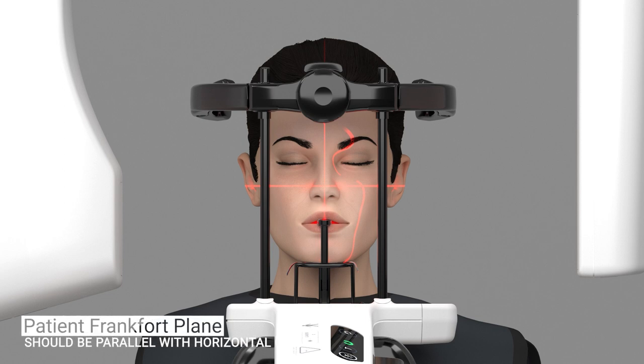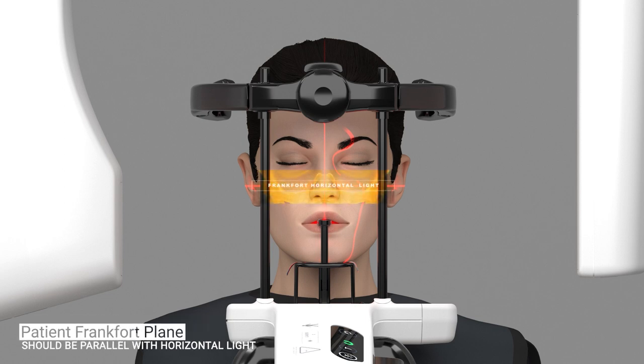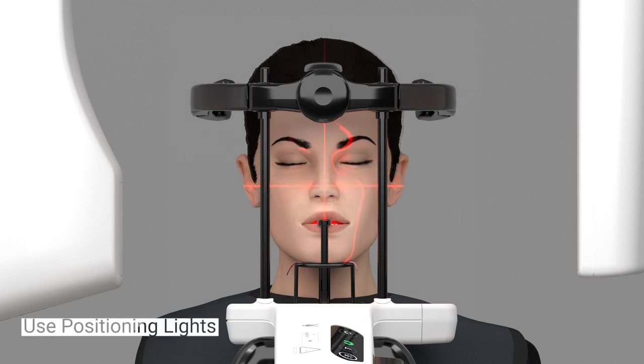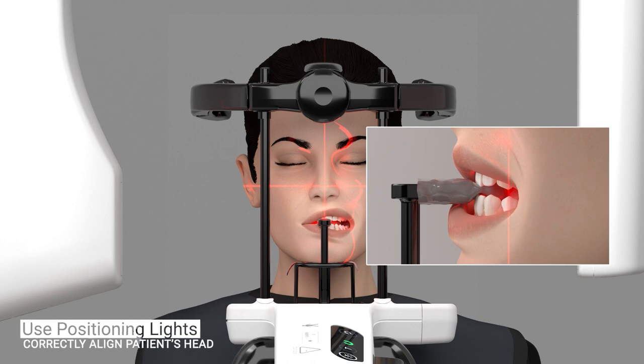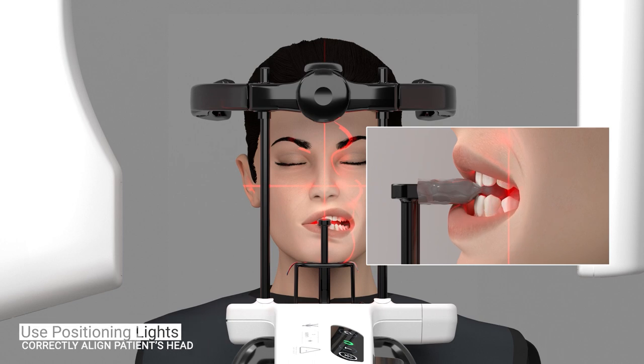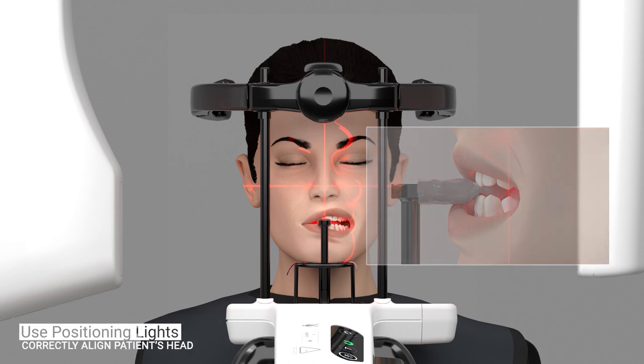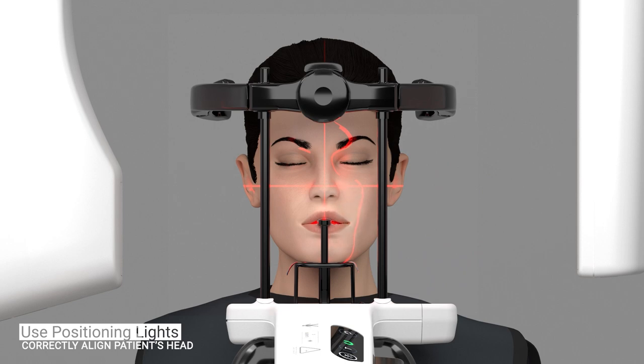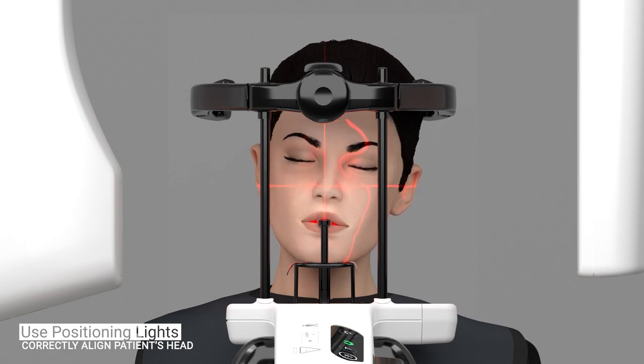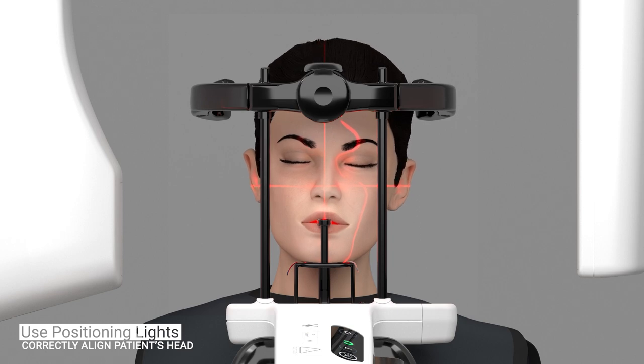The patient's Frankfurt plane should be close to parallel with the Frankfurt horizontal light. Align the patient so that the root tips of the lower and upper incisors are vertically aligned and parallel to the tilt light. Ensure the patient's head position is aligned with the mid-sagittal positioning light. The head should not be turned or tilted. Compensate for misalignments by manually moving the patient's head into the proper position or by adjusting the unit height.